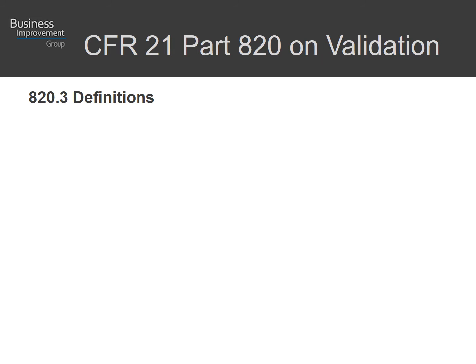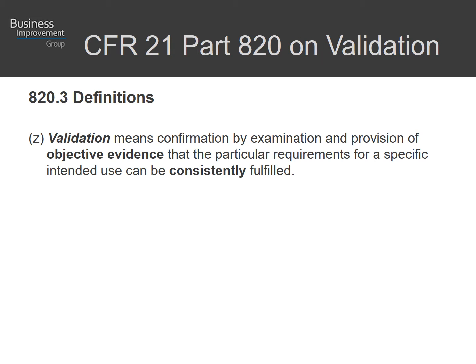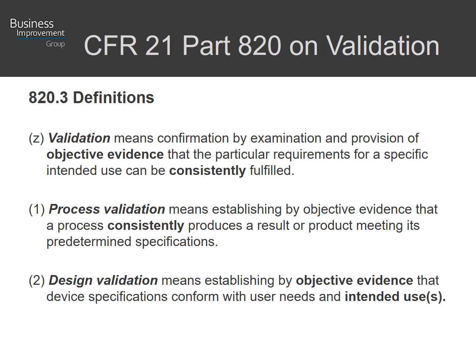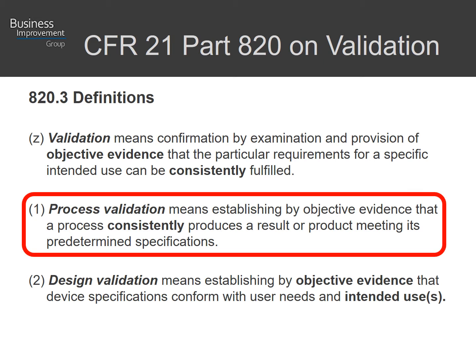Some definitions the FDA provides in this guidance document: validation is using objective evidence to demonstrate that requirements are fulfilled consistently. Process validation means establishing by objective evidence that a process consistently produces a result or product meeting predetermined specifications. Design validation uses objective evidence to show that specifications conform to the user's needs and intended use. For this project, we'll focus primarily on process validation and discuss how design of experiments can support that activity.